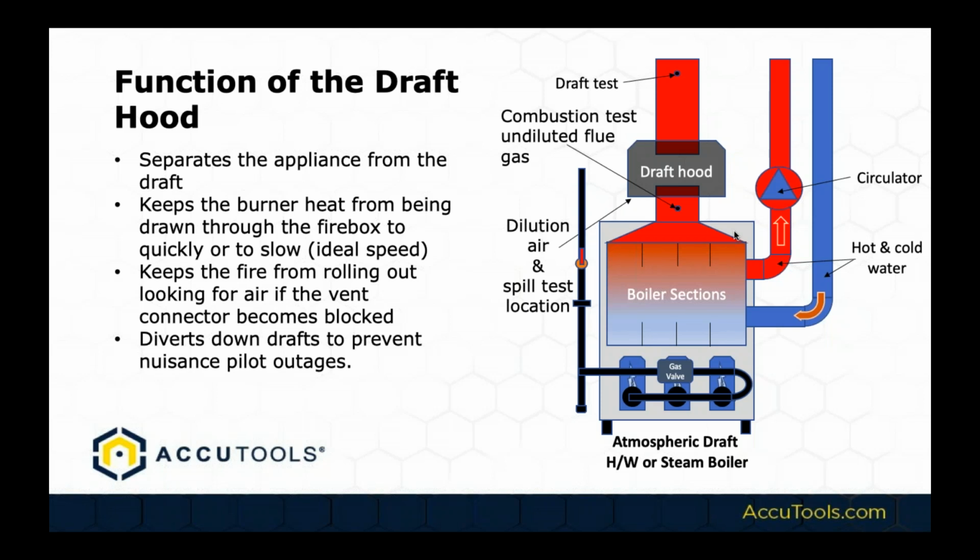And the function of a draft hood is to separate the appliance from the draft. When you're looking here at where this draft hood is, you've got the top of the flue coming off, and then you've got this open space, and it physically separates the appliance from the draft. What happens here is, as the fuel's burning, the hot flue gases rise up at a perfect rate, right? Because they designed the combustion chamber in there to control the velocity of the flue gases going up to the furnace. So this is an engineered solution.